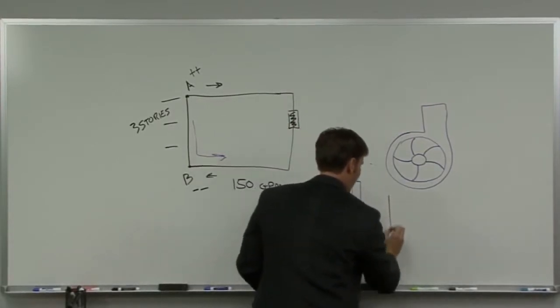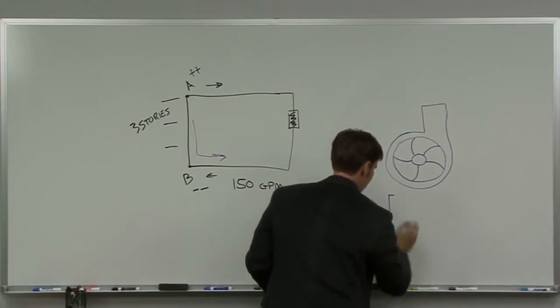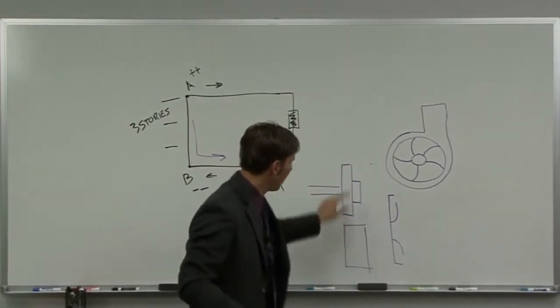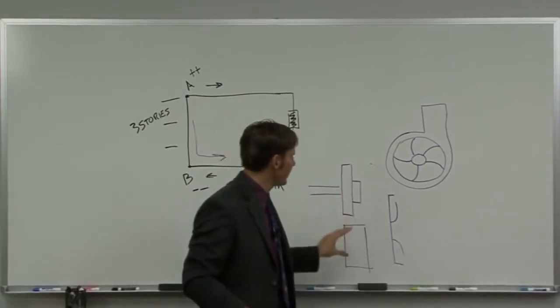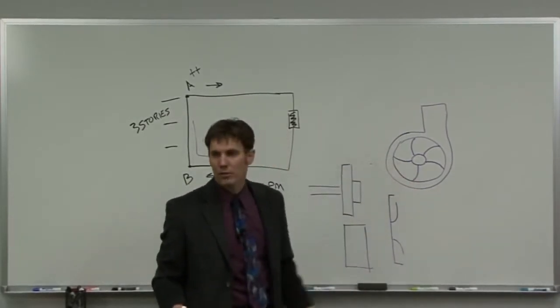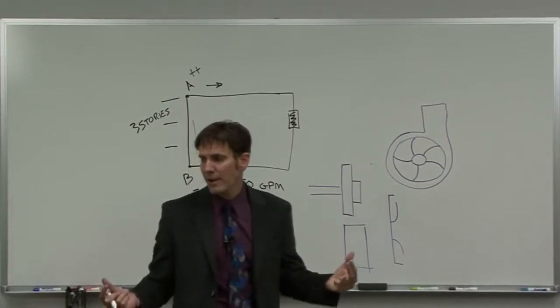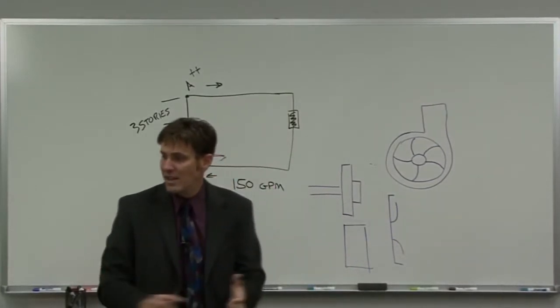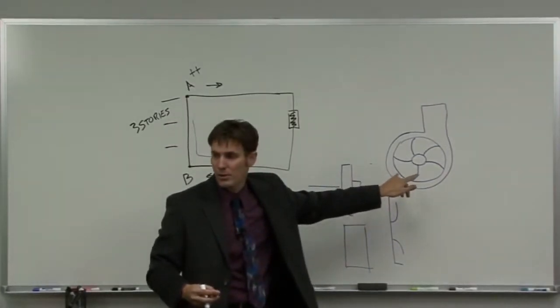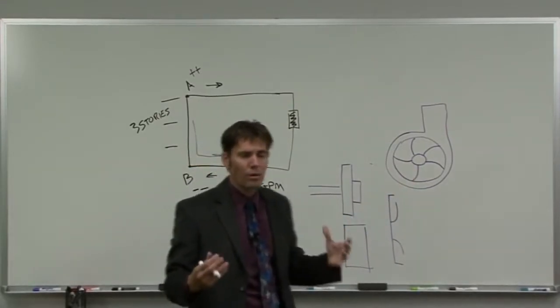Is it an open impeller? And we've got our vanes that are attached here. Is it a closed impeller? All of these will define what my pump curve looks like. So when we look at a manufacturer's pump curve, it's all based on these two components. It really has nothing to do with the motor. The motor is there to drive it.